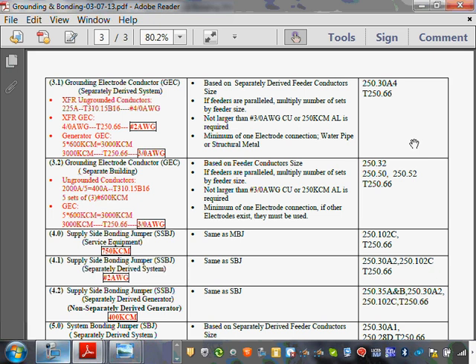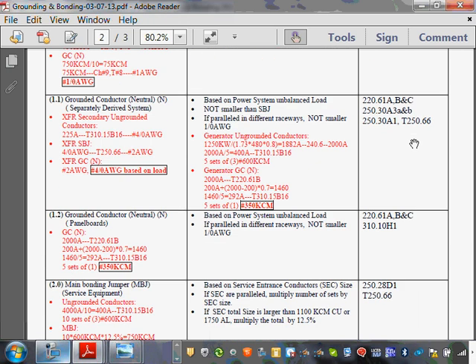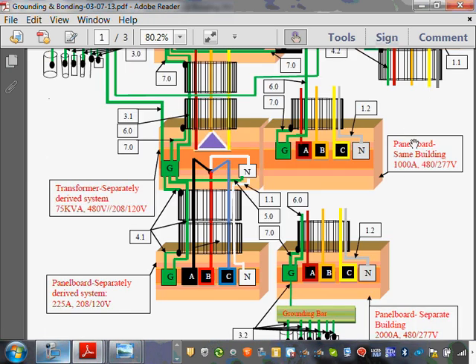Oh, yes, sir. Let's say you take that bottom panel board on your drawing and turn that into an isolated ground panel board. I had this actually happen not too long ago. I wanted my isolated ground conductor to go all the way to the building entrance grounding bar, and the AHJ wanted me to ground it to the transformer, because there was a transformer there. Anyway, he let me do it my way, but he was a little concerned about that. I didn't want to tie it to the transformer, because some of the equipment was tied to other equipment not on that panel board via Ethernet cables and so on.